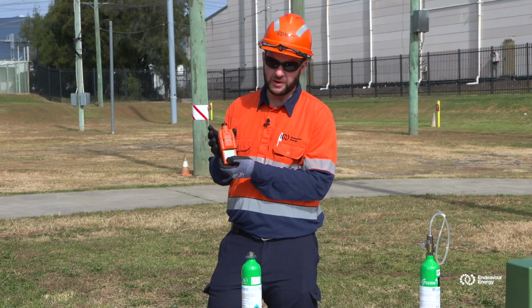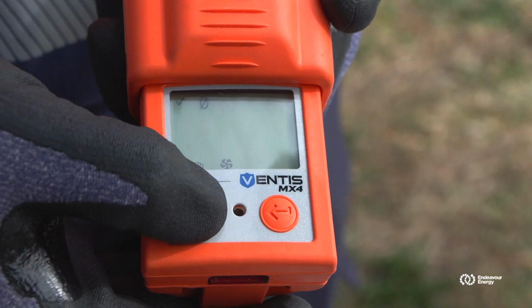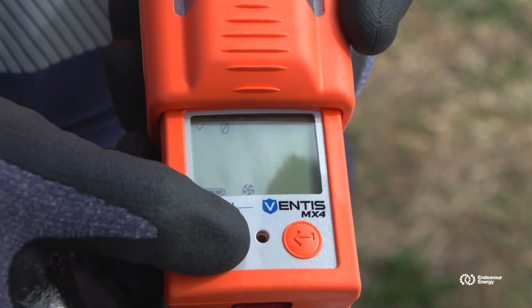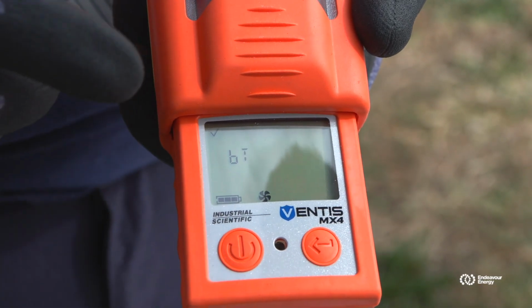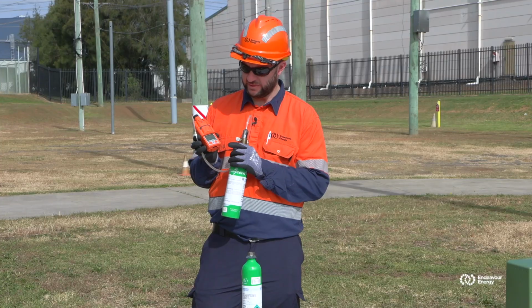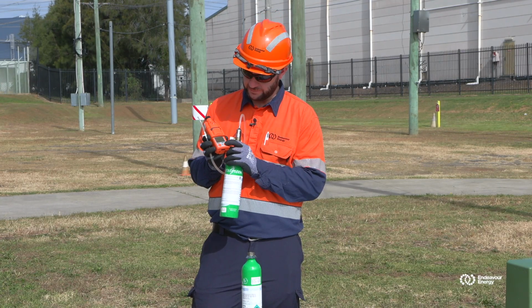What we're going to do now is set up to go to the bump test. To conduct the bump test on the gas detector here, we scroll through and we'll end up on a screen which has BT on it. To enter the bump test mode, we press the return key.